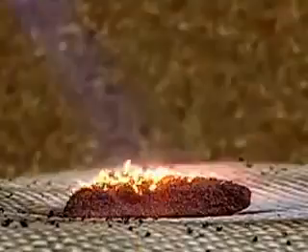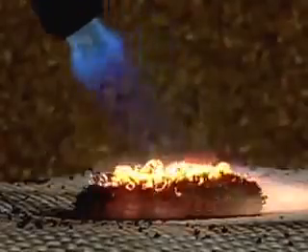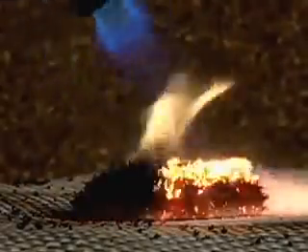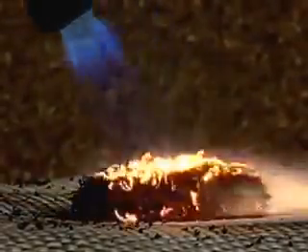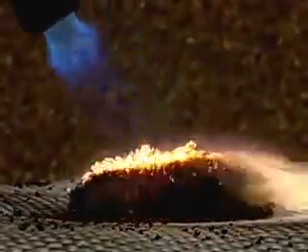So, how are combustible penetrations in a fire barrier restored to their original rating? By using Firestop materials designed to expand with heat in a process called intumescence. This technology permits rapid expansion in the presence of heat so that voids created by the melting combustibles can be sealed by the intumescent material.